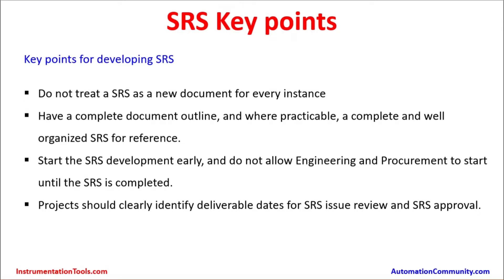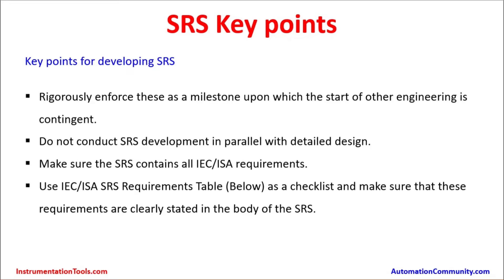A clear timeline must be given for SRS issue review and approval. Rigorously enforce these as milestones upon which the start of other engineering is contingent — SRS development must be completed well ahead before the next project phase begins. Do not develop the SRS in parallel with detailed design. It is better to first identify instruments based on SIL category, voting configuration, and type and number of instruments, then proceed — SRS should not be done in parallel with process engineering.